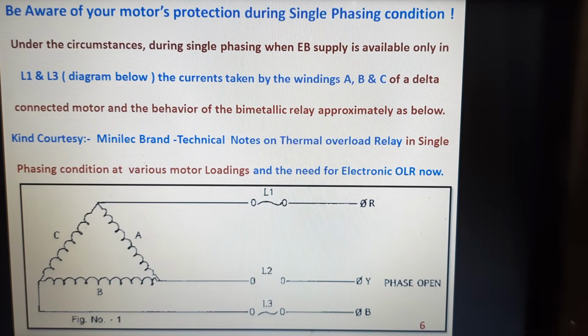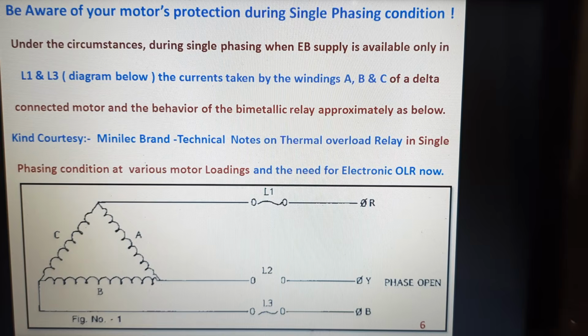Be aware of your motor protection during the single phasing condition. Under the circumstances during single phasing, when the EB supply is available in L1, you can refer to the figure at the bottom. At L1 and L3 only the supply is available, and the L2 phase is open. The current undertaken by the windings A, B, C on the delta connected motor, and you can see on the next page how the motor is behaving at different types of loading.